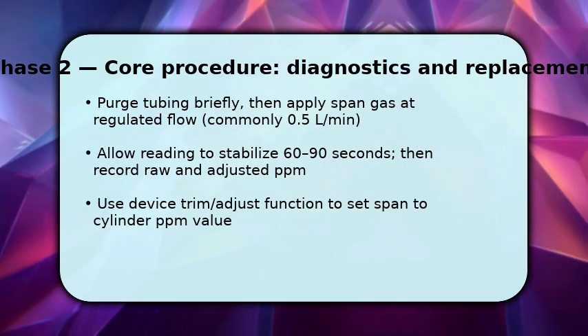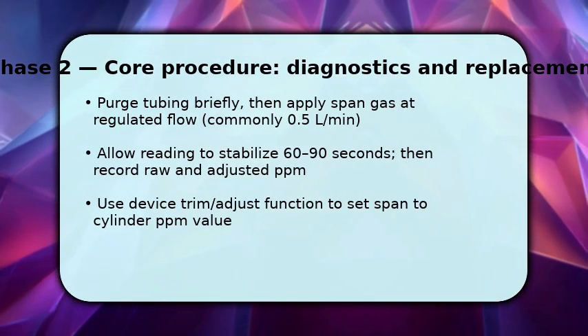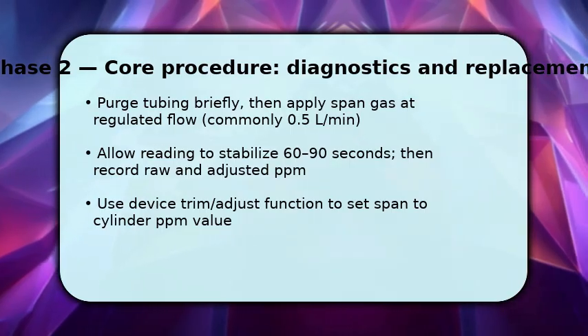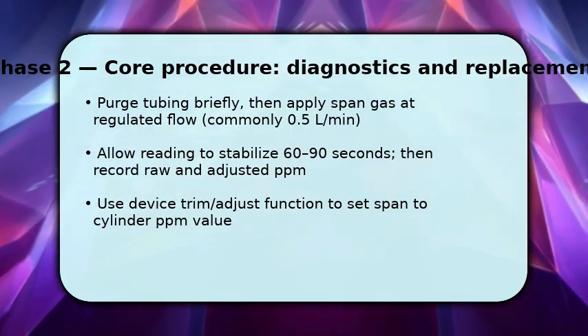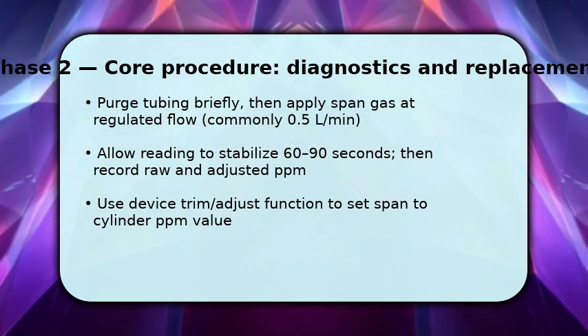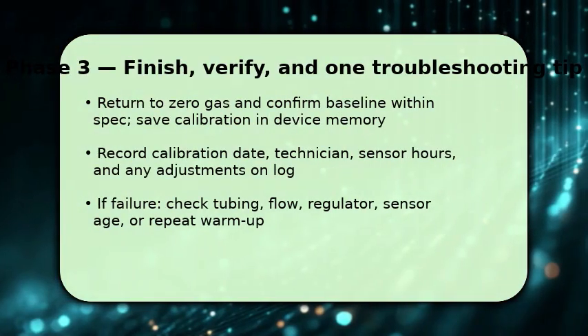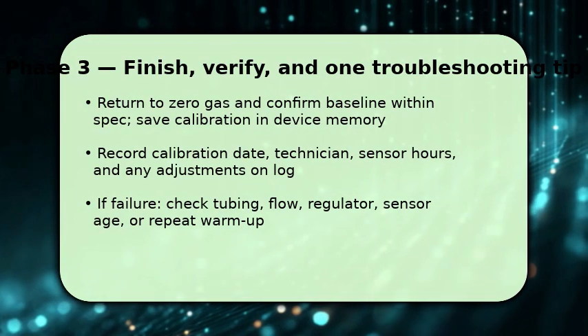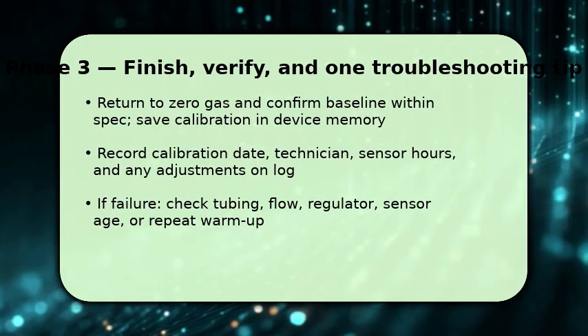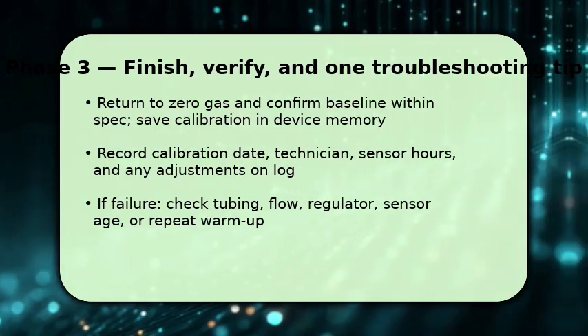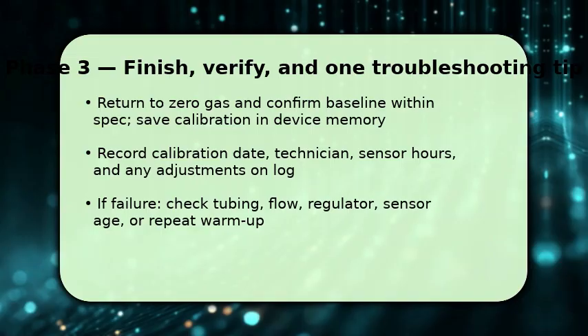If the reading won't reach target, confirm flow, cylinder concentration, and that the sensor is healthy. Then repeat the span step until accurate. You finish by returning to 0 gas to confirm the baseline is within the manufacturer tolerance, and then save the calibration settings to memory. Make sure the unit exits CAL mode properly.